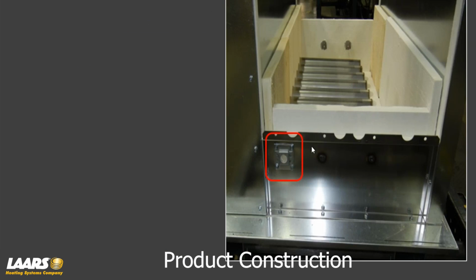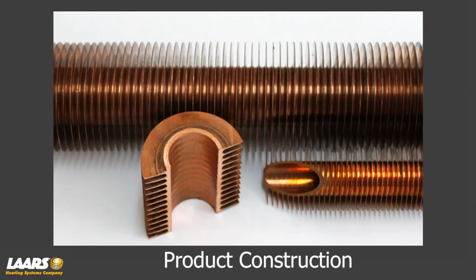Now, also on the construction, we do have a sight window. That sight window is down in the lower right-hand side, so you could look in and see your flame pattern. If you ever had any questions with that, you can look into the heat exchanger or combustion chamber area and look at your flame pattern. Next, I want to talk about the heat exchanger.